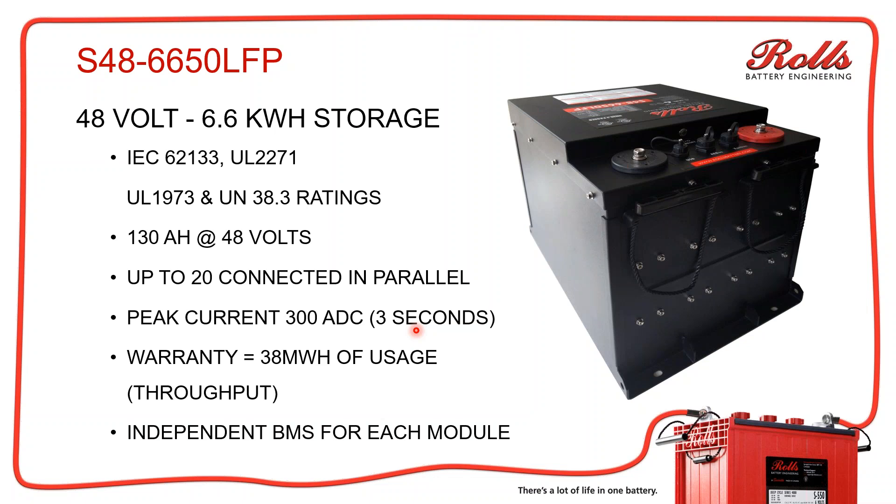The next one is the 48-volt module, the S486650 LFP — that's 48 volts and 6.6 kilowatt hours of storage. It is also rated IEC 62133, UL 2271, UL 1973, and UN 38.3. It is also IP55 rated. This is a 130 amp hour battery at 48 volts, and again, 20 can be connected in parallel with a peak current of 300 amps DC. The warranty on this one is 38 megawatt hours of throughput, and it still has the independent BMS for each module.